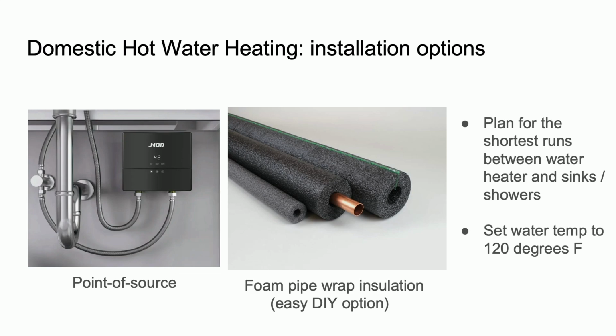If you crank it to 140, which I see a lot, at 120 degrees it takes 5 minutes to get scalded by hot water. If you have 140 degree water, it can scald you in 5 seconds. So it's definitely a safety thing, you do not want it to be 140. And also it's costing you a lot more money to heat the water in the tank to that temperature. So don't do that.